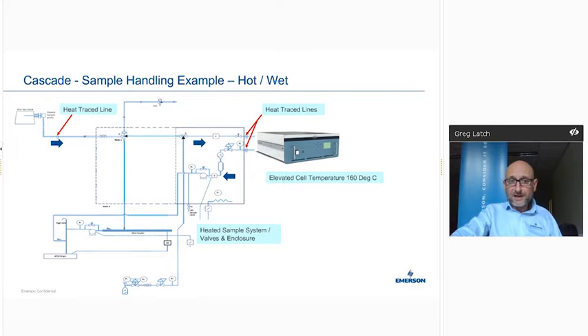We're compensating for anything that's within that cell because we do understand our gas composition, which we'll touch base on shortly thereafter. And then as you can see, we manage the pressure. Obviously, gas density and components of interest have to be managed at a particular known pressure and temperature, hence the 160 degrees C. We go through a little RC network post measurement just to help assist any pulses that may happen in the system, depending on the operation, and also the pump. And then from there we go through to a vent header. And all the liquids are then managed post-measurement, not before, which is a little bit different to what's traditionally happened.